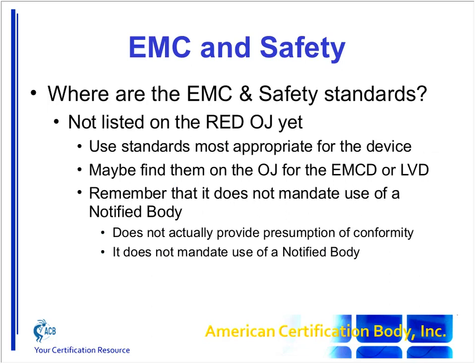And the same with other EMC standards. So for example, if you have an IT product which contains a radio, and so maybe you're also testing to EN55032, for example, well, just because that standard's not listed on the red OJ, it's still the correct standard to use for your product. Similarly, if you have a washing machine or a refrigerator, a good place to look would be to go to the EMC Directive and Low Voltage Directive official journal, and you probably find some good, useful standards on there to use. Just use the standards that are correct for you, and remember that you do not need mandatory use of a notified body based on that.